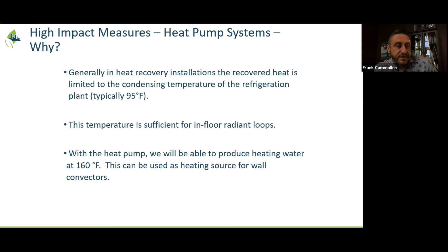But with the heat recovery chiller or heat pump, you'll be able to produce higher temperature water, about 160 degrees or so. And this is where it's a bit of a game changer, because this 160 degree water can be used pretty well anywhere within the facility, or at least it is a sufficient temperature to be used anywhere in the facility. Usually, what we've seen is that a lot of the heating is provided by convectors on the perimeter, and typically they're designed for about 160. So this works out really well. Again, that's usually for peak loads, but this heat pump or heat recovery chiller allows you to make the most of the heat that's recovered from the refrigeration system, making it usable because of the higher temperature for space heating. Again, as that graph showed, with this concept you can offset most, if not all, of the gas-fired heating in the facility.